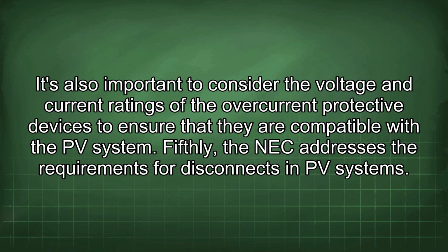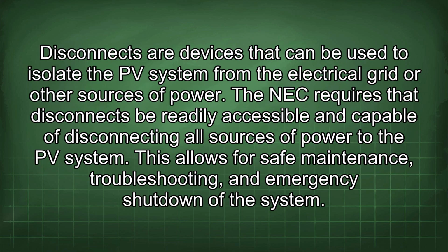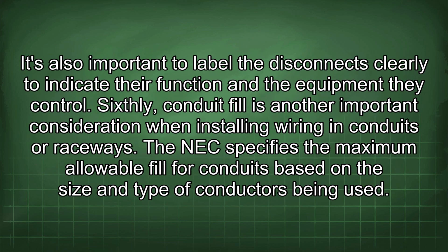Fifthly, the NEC addresses the requirements for disconnects in PV systems. Disconnects are devices that can be used to isolate the PV system from the electrical grid or other sources of power. The NEC requires that disconnects be readily accessible and capable of disconnecting all sources of power to the PV system. This allows for safe maintenance, troubleshooting, and emergency shutdown of the system. It's also important to label the disconnects clearly to indicate their function and the equipment they control.